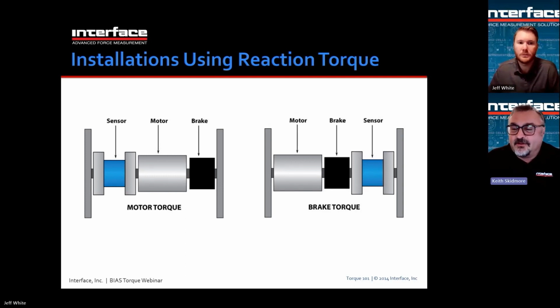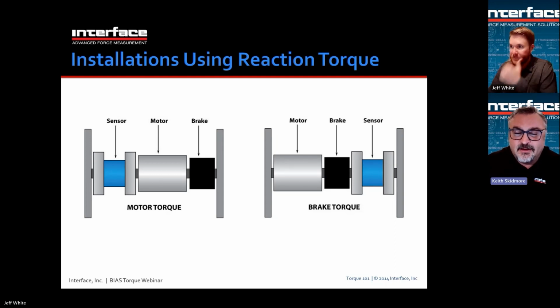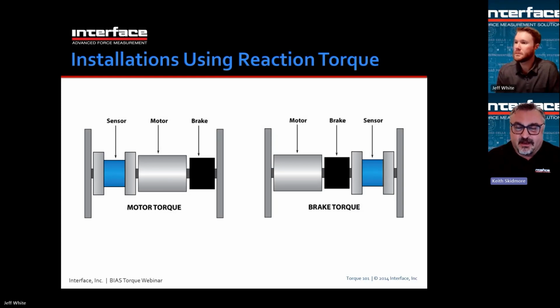These are some other examples of using static or reaction torque sensors to measure rotating torque. On the left side, we have motor torque, and on the right side, we have brake torque. You can see they both have the same components: a motor, a brake, and a torque sensor, but the difference is what is intended to be measured. On the motor torque side, we're trying to measure how much torque or power the motor produces. So we can mount the housing of the motor to the torque sensor. The torque sensor is rigidly mounted to the plate on the left side. The housing of the motor is rigidly mounted to the top of the torque sensor on the right side. And then the brake is mounted to the plate on the right side. So the motor shaft is spinning, the brake engages, and you can use the brake to load the motor and measure how much motor torque there is.